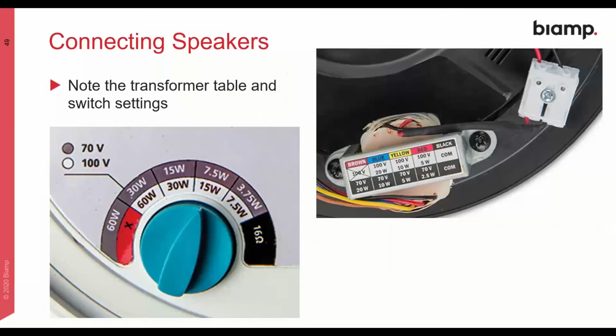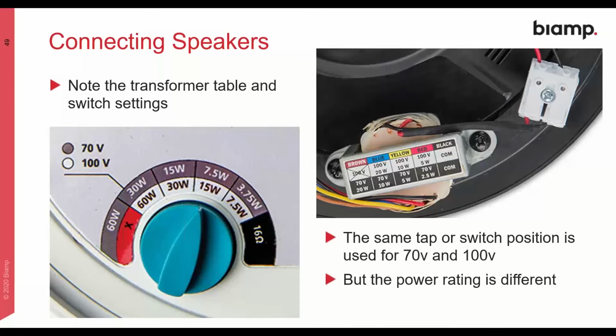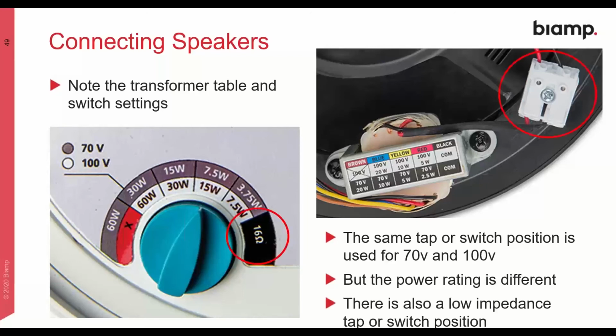Also note the transformer table and switch settings here. The same tap position is used for 70 volt and 100 volt, but note you have a different power. For example, on the yellow connector on the transformer, you have 100 volt at 10 watts, but at 70 volts, it's 5 watts. That's because of the lower line voltage and therefore the lower current, resulting in lower power for that tapping. So it's interesting to note you use the same connection, but the power rating really does depend on what voltage you're supplying it with.